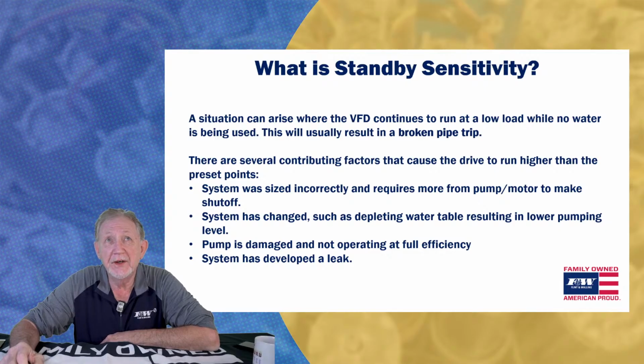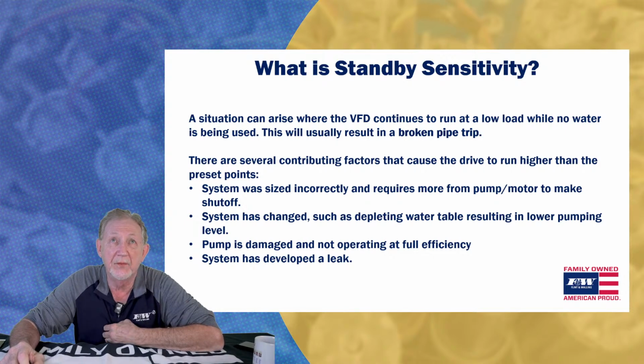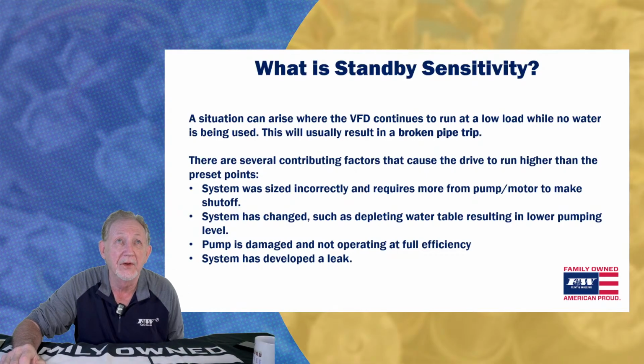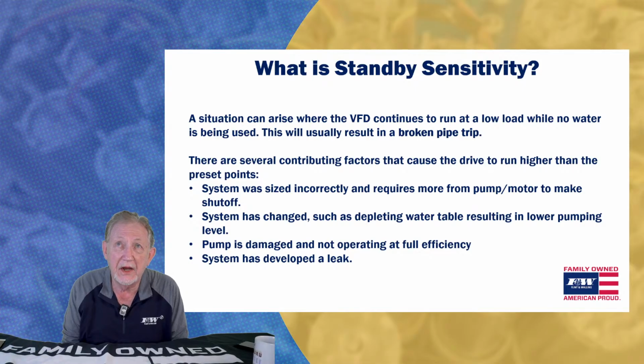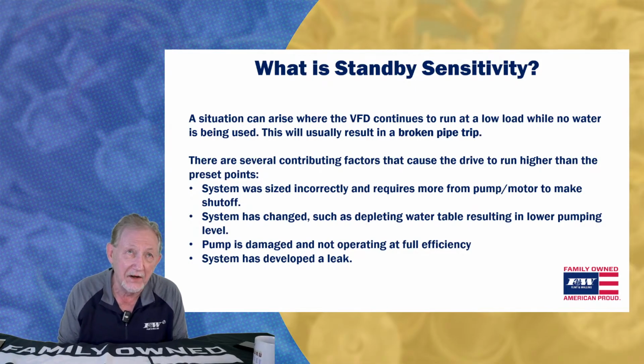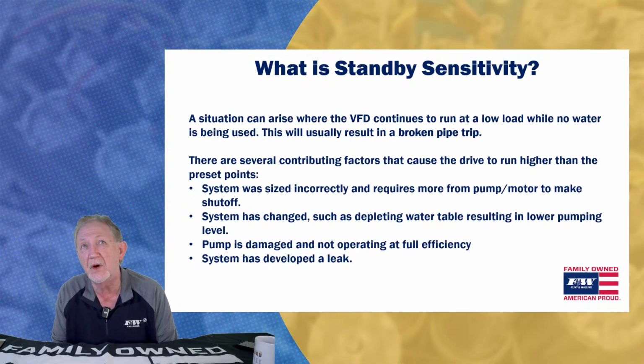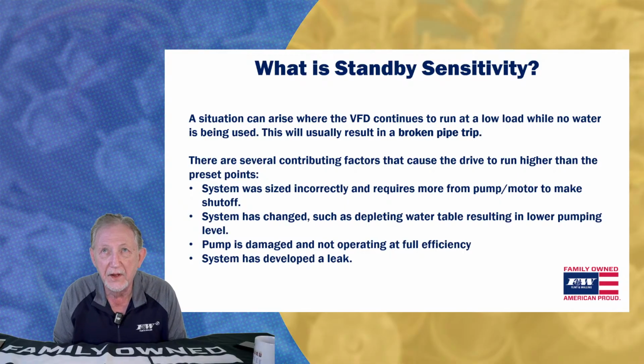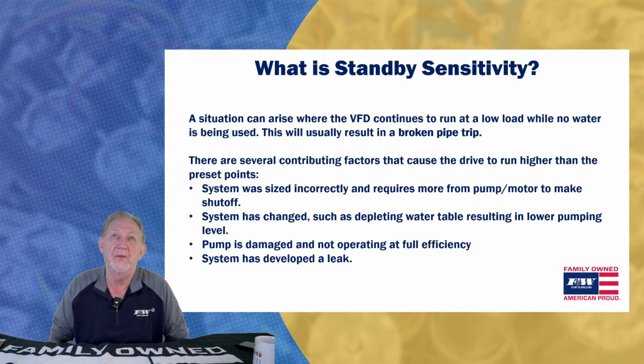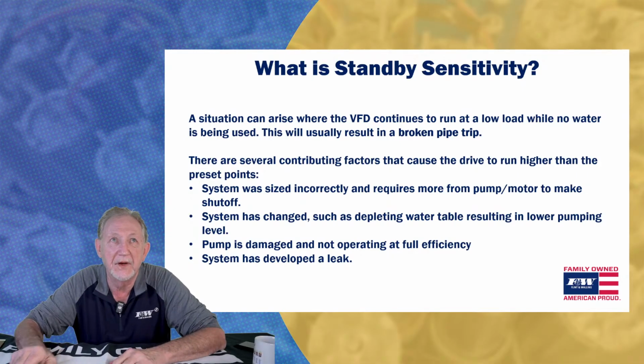It says here a situation can arise where a VFD will continue to run even when no water is being used, and what typically results is a broken pipe trip. All right, so the drive continues to run under a low load. There are several factors that can cause the drive to run higher than the preset points. Higher, keyword, higher than the preset. If the system wasn't sized properly to begin with, you need more motor and pump to make the shutoff.